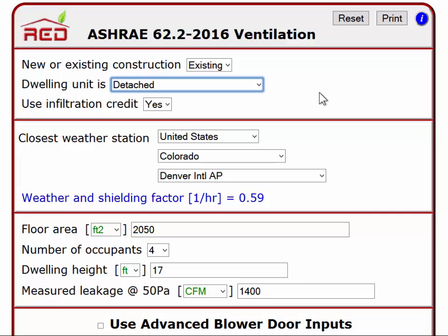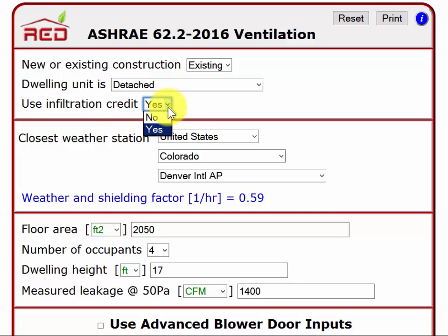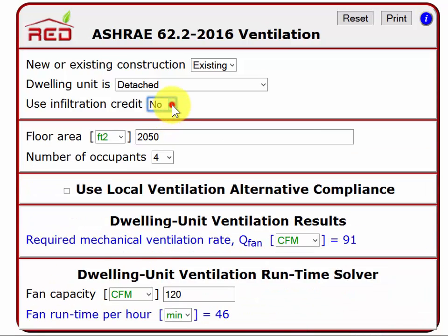Please watch the extended video tutorial for more detail on that. The next and final input for this section of the tool is use infiltration credit. You have a choice of yes or no. We recommend that you choose yes for most cases. One case when you would choose no would be a multi-family building that has dwelling units that are stacked — that is, one above the other. The ASHRAE standard does not allow any infiltration credit for stacked multi-family dwellings, so in that case you would choose no. Otherwise, we recommend that you use yes.